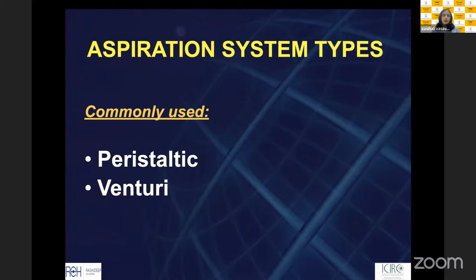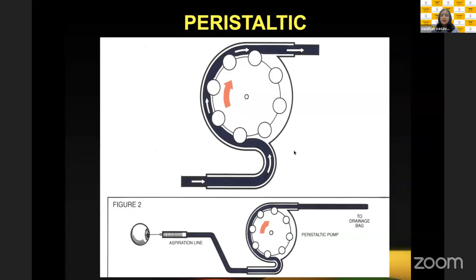So like I said, peristaltic and Venturi. What are the characteristics of a peristaltic machine? Because most of us will have access to that. You may have read this in your textbooks and seen it in the machine cassettes or the machine body: there is a set of rotor valves that pinch a tube and cause the flow of fluid. So there is one aspiration line that comes from the eye and sucks fluid, and depending on the speed at which these rollers pinch the tube, you can decide the speed at which they pump. Accordingly, the fluid is drained out of the eye to the drainage bag in the machine. So this is a basic fundamental.